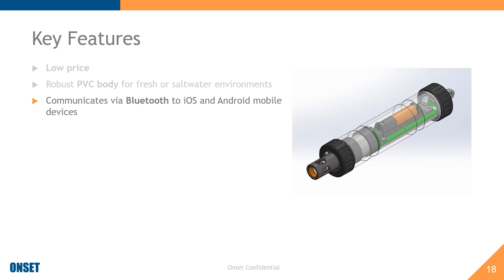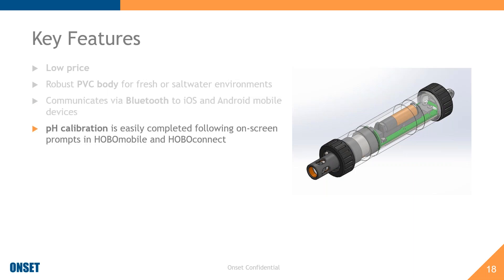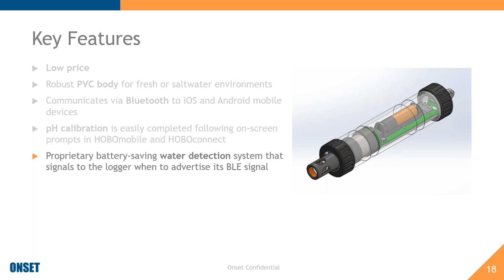It has a robust PVC body suitable for fresh or salt water environments, and communicates via Bluetooth to an iOS or Android mobile device. pH calibration is quite easy — even the marketing guy was able to figure it out without looking at the instructions. The app gives step-by-step instructions. It has battery-saving technology, going into low-power mode when submerged, and a glass bulb electrode. Logging intervals range from one second to every 18 hours, with 152 kilobytes of memory. The app will tell you how long you can expect to log continuously at whatever logging interval you select.